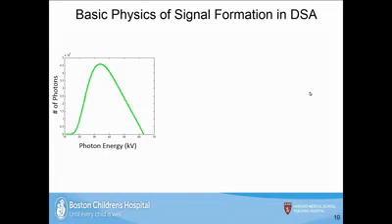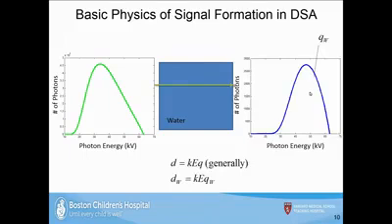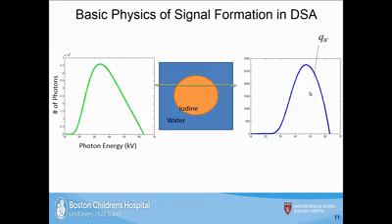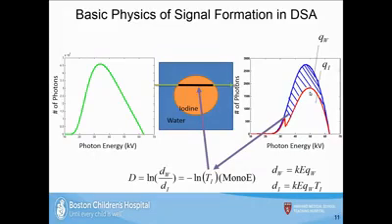We use poly-energetic rather than mono-energetic beams. For signal formation on a per-pixel basis: for DSA, an energy spectrum at 63 kV is projected through 20 centimeters of water, giving a spectrum at the detector. When iodine is injected and a contrast image is acquired, DSA essentially takes the difference in area between the two energy spectra, yielding the logarithmic projection of the iodine transmission factor — using a mono-energetic approximation.